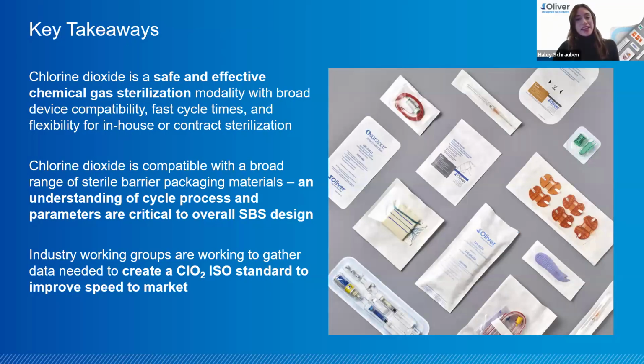All right, so some final takeaways, and then we'll move into Q&A. Chlorine dioxide is a proven safe and effective method for sterilization of medical devices today with broad device compatibility, and there are advantages in the form of fast cycle times and flexibility in where a device gets sterilized in the manufacturing process. So options for in-house as well as contract sterilization. It's also compatible with a broad range of sterile barrier packaging materials, as we just reviewed.